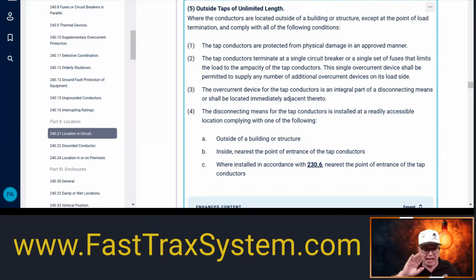So get that out of your head. It's automatically going to be equal to whatever the overcurrent device is it terminates, because you have to make sure that it has the ampacity that is going to be protected by the overcurrent. It says it right there.